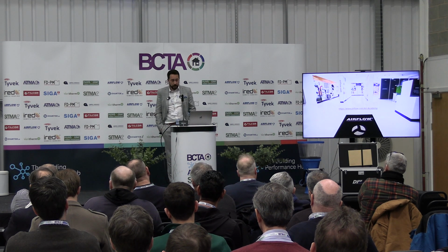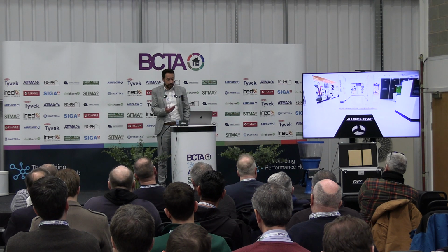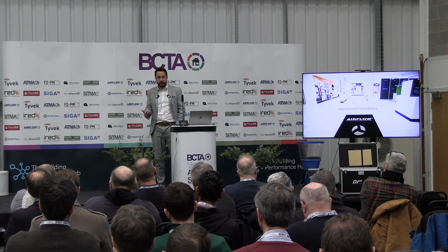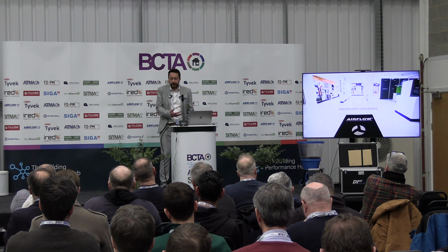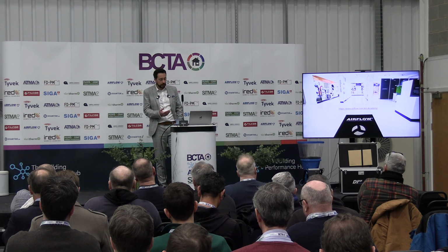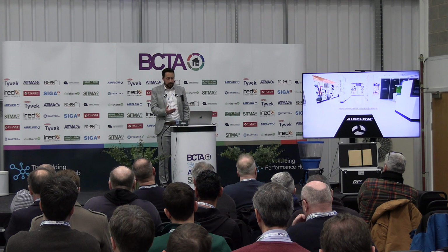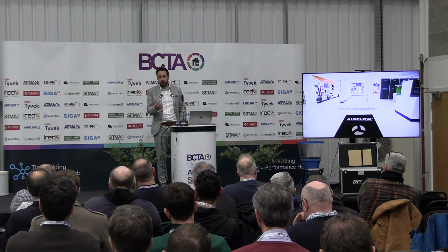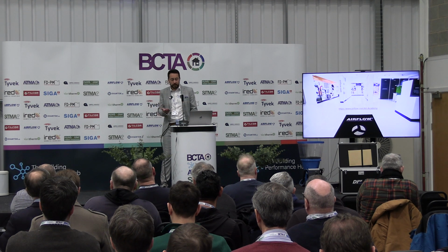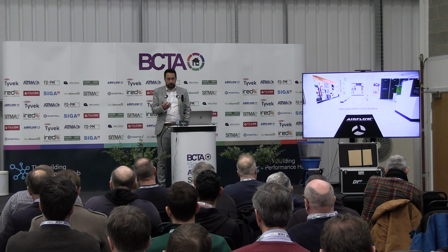Yeah, so that's one thing that always gets forgotten about because of the name of the product. Because the name of the product is a heat recovery unit. Everybody does forget that it can also recover the cool air. So in the summer when it's warmer outside than it is inside, the units can utilise the cooler indoor air to cool down the air coming in from outside. So in terms of cool recovery, they do that via the summer bypass of the units.